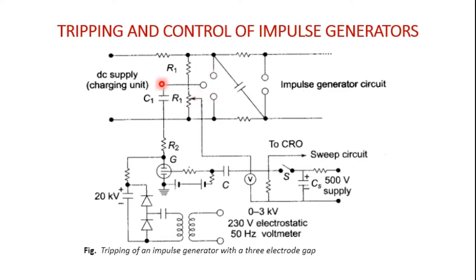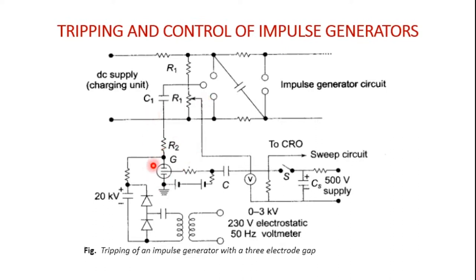The generator is fitted with a DC supply charging unit having a three electrode gap arrangement. The third electrode is kept between the top and the bottom electrode, and with the help of resistances R1, a certain potential is maintained between the top and bottom electrodes. When a tripping signal is initiated by a pulse from the thyratron by closing switch S, conduction begins.